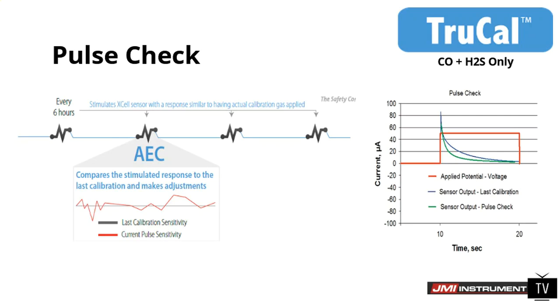If it falls outside of tolerance and needs to be calibrated, the sidebar lights of the transmitter will pulse a slow green pulse to give a visual indication that it needs to be calibrated. And if the sensor falls within its own tolerance, where it can adjust for the sensitivity loss, whether it be temperature and humidity or electrolyte loss, it'll make that change internally and you won't even see it, and it'll just keep on trucking.